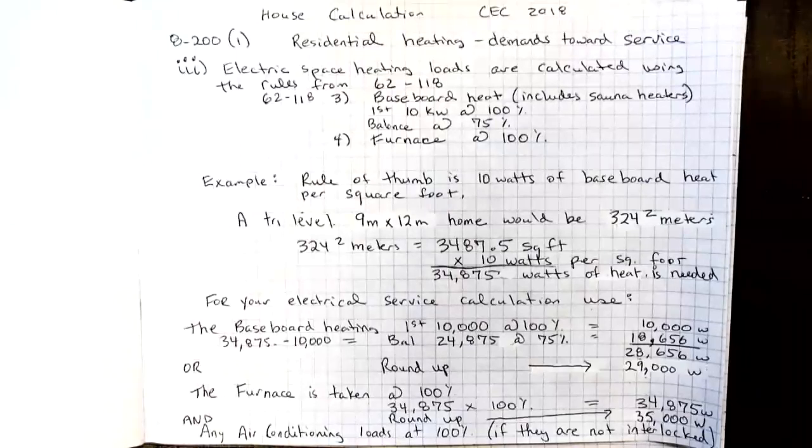We take the first 10,000 watts at 100% and the balance at 75%. The reason for this adjustment is because baseboard heat has its own thermostat, each baseboard heater, each area. That means they're going to cycle on and off and they're not always going to come on at the same time.